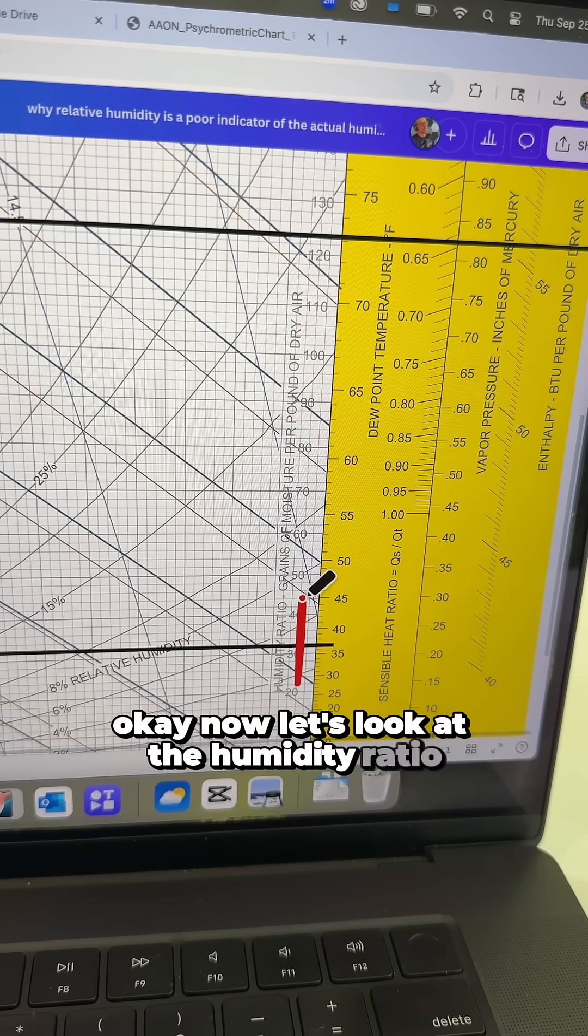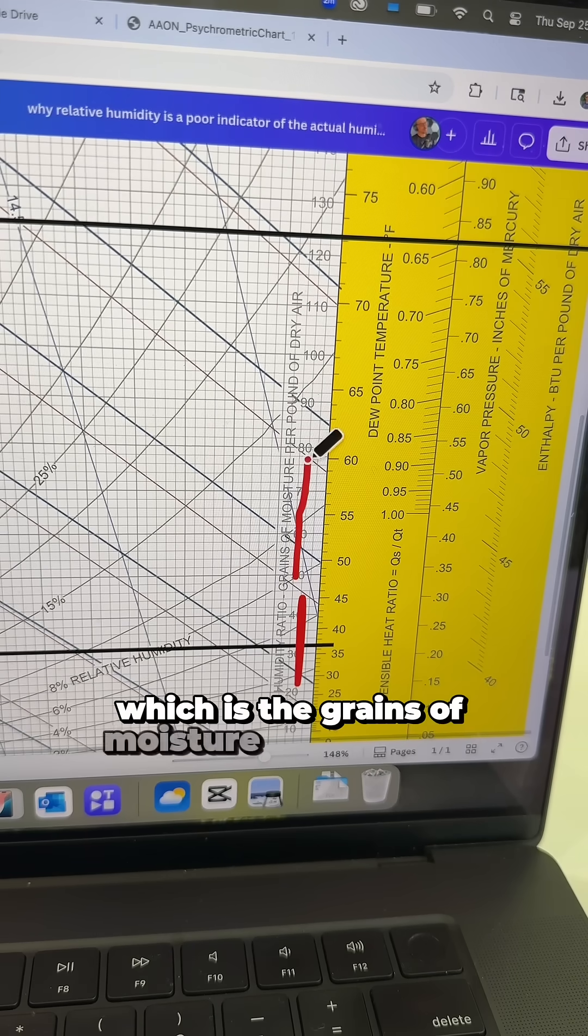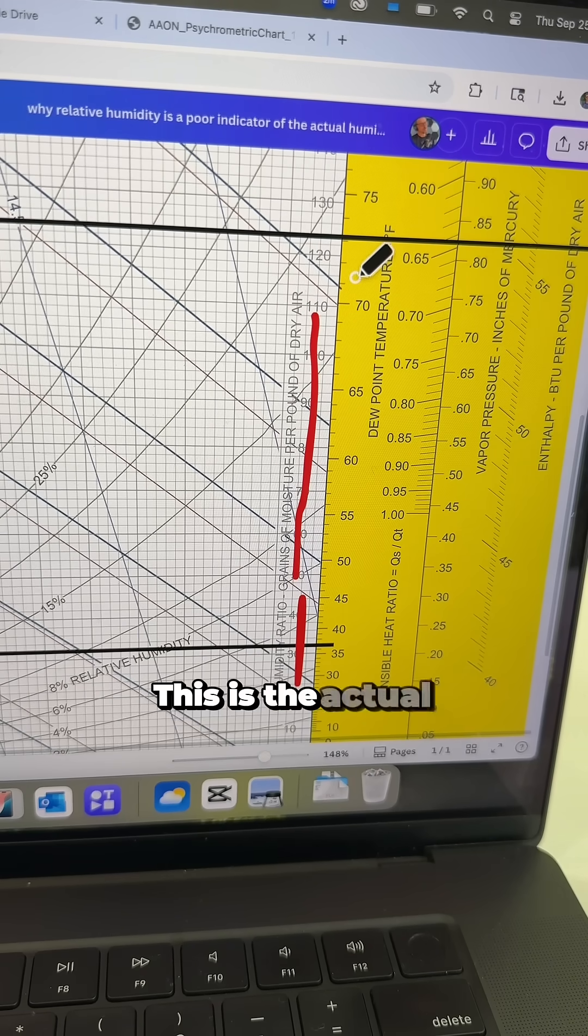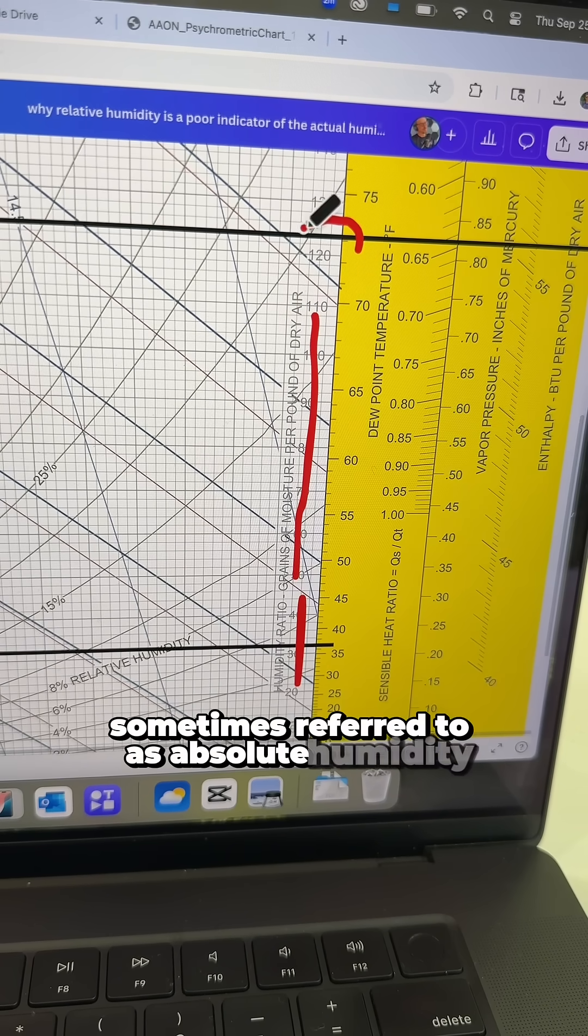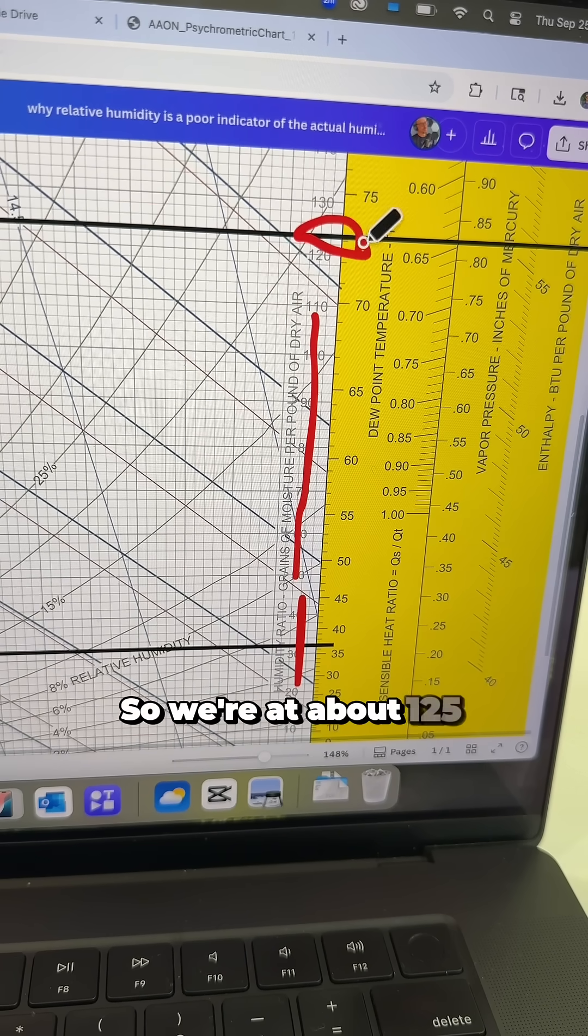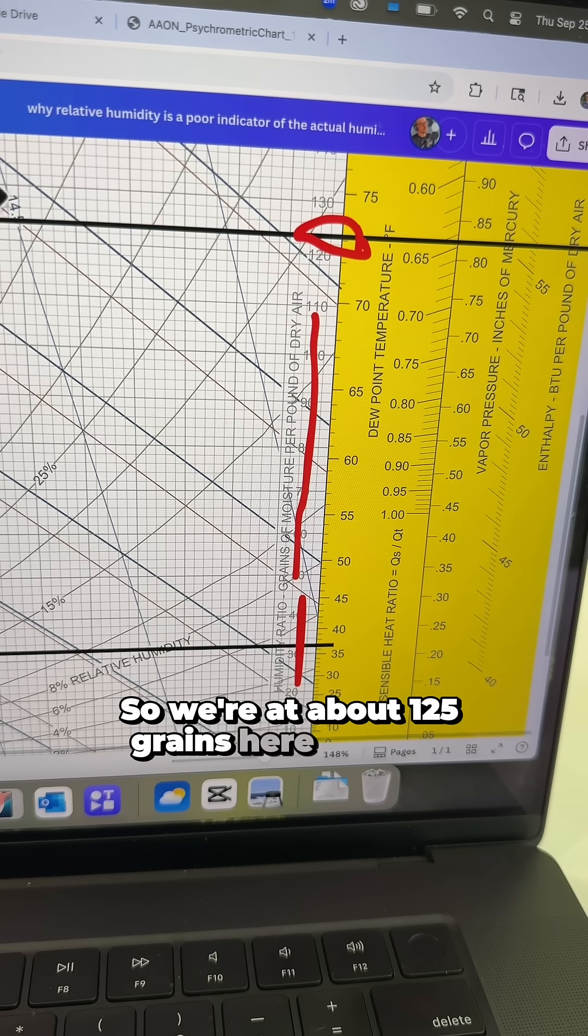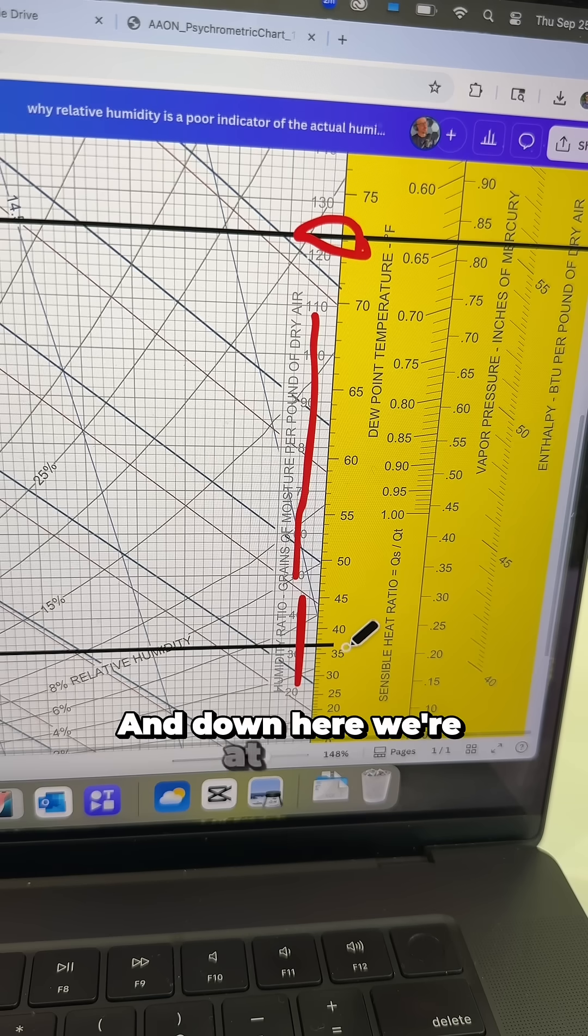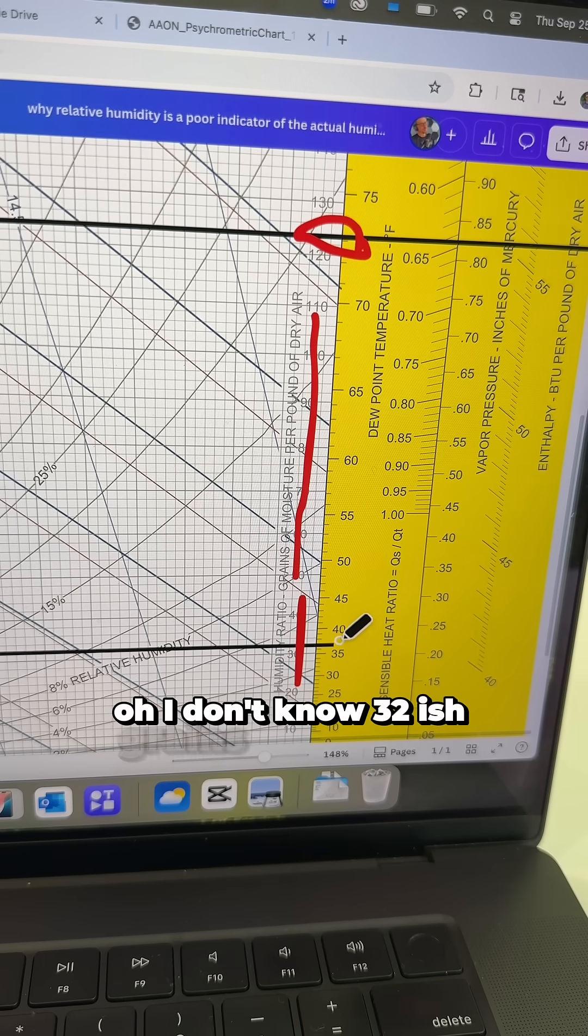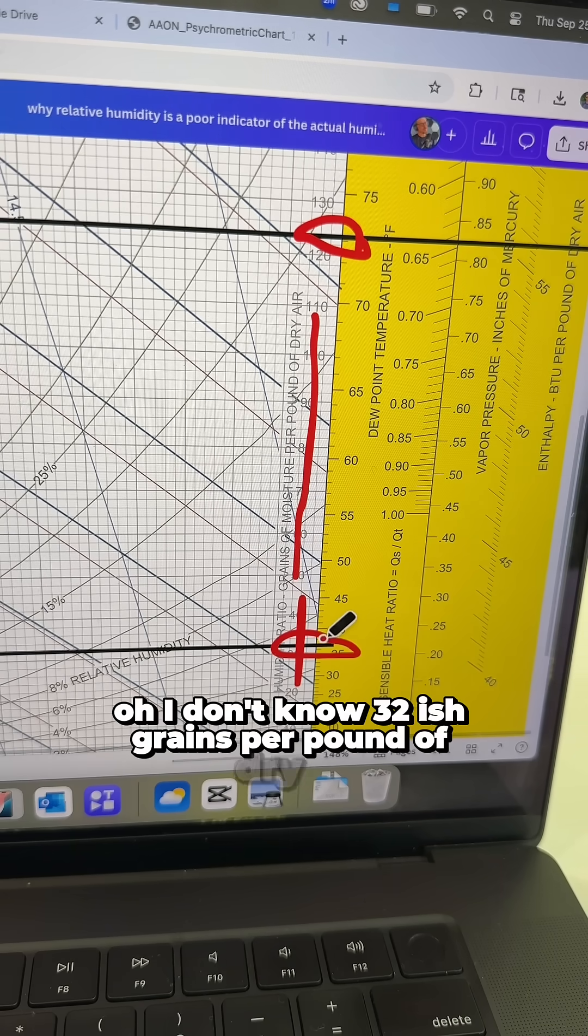Now, let's look at the humidity ratio, which is the grains of moisture per pound of dry air. This is the actual amount of moisture in the air in terms of grains, sometimes referred to as absolute humidity. So, we're at about 125 grains here at 95, 50%. And down here, we're at about, oh, I don't know, 32-ish grains per pound of dry air.